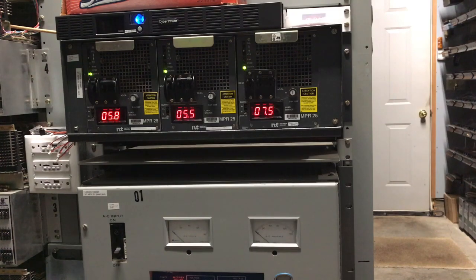I've been in central offices with incredibly huge, high amp capable DC power plants. When working on any power system with batteries, there's the fused side and the non-fused side, which is typically the load. This is not something I recommend if you have no power experience, even considering touching it. Things can go wrong very fast, with potentially fatal results.